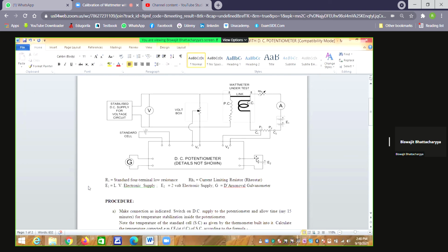Now, why is contact resistance important in the current terminal and not in the potential terminal? Because in the potential terminal, the current drawn by the voltage measuring circuit is insignificantly small, so no extra current is present and the contact drop is insignificant.